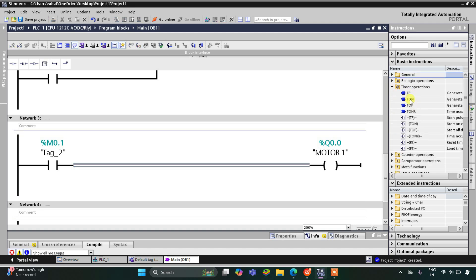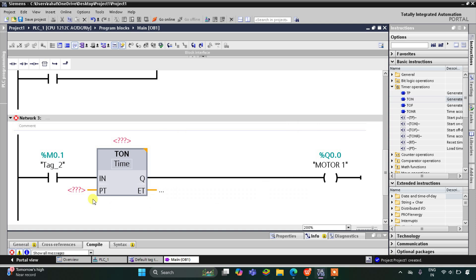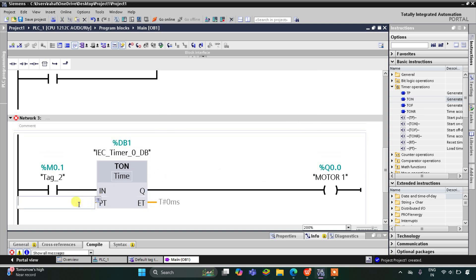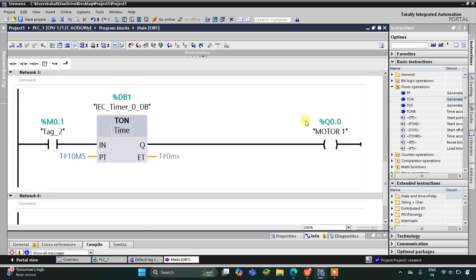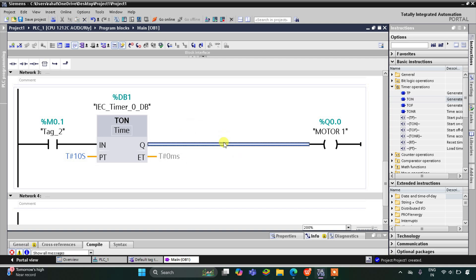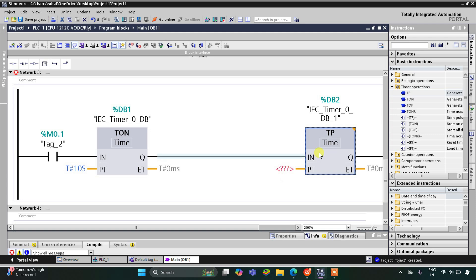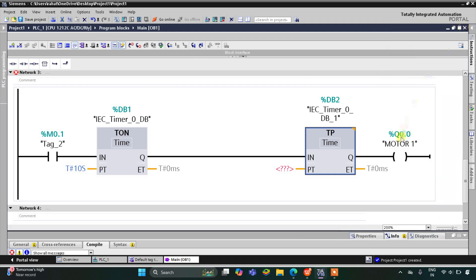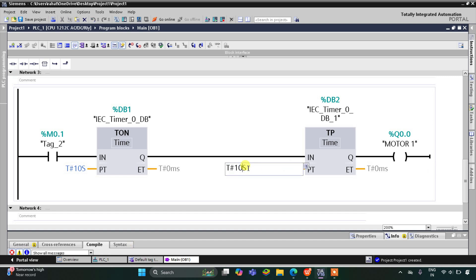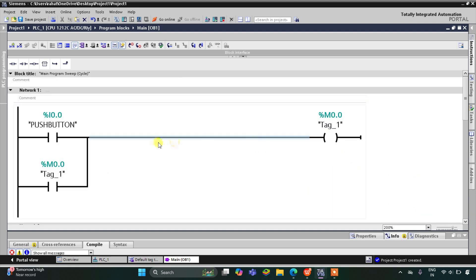Motor 1 should turn on after 10 seconds, so I will use a timer. I'll go to Timer Operations and select T-ON. The preset value should be 10 — that is, when push button is pressed and released, Motor 1 should turn on after 10 seconds. It should also remain on for 10 seconds, so I will insert a TP pulse timer here. The preset value should be 10 seconds — not milliseconds, 10 seconds.